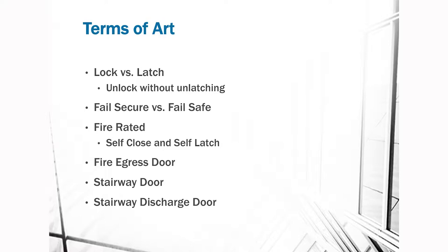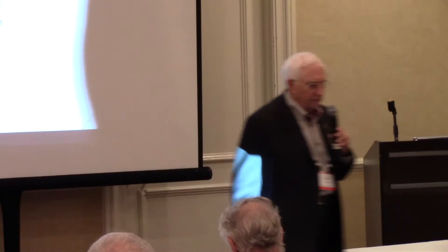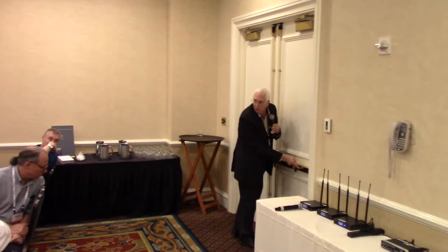Fire-rated doors must self-close and self-latch — those doors have door closers and latches. The doors in this room are fire-rated and were ordered correctly, so there's no hole for a holdopen device. But one door is open right now because somebody has dogged it. So we're in a room that's technically dangerous because that door is dogged open.